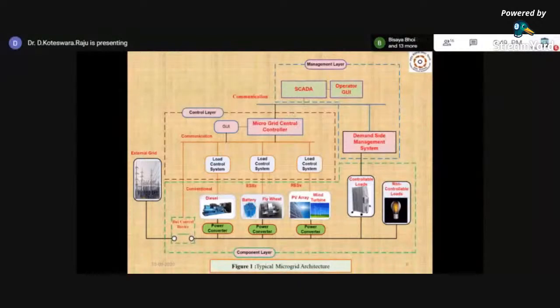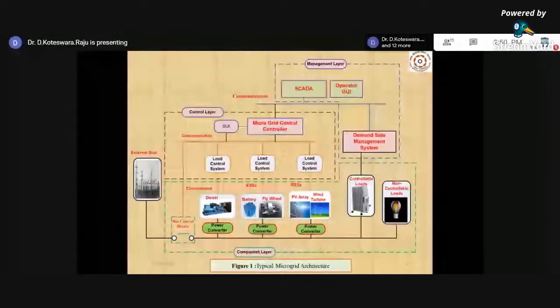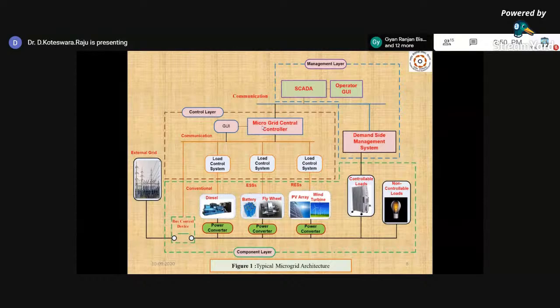It is the microgrid controller's job to compare the total generation of these distributed resources and the load demand within the microgrid. If the generation is less than the loads, it will shut down the non-critical loads and try to supply the critical loads, and vice versa.